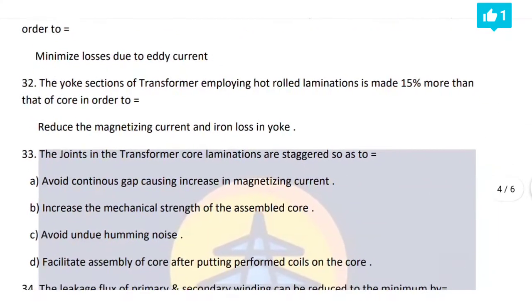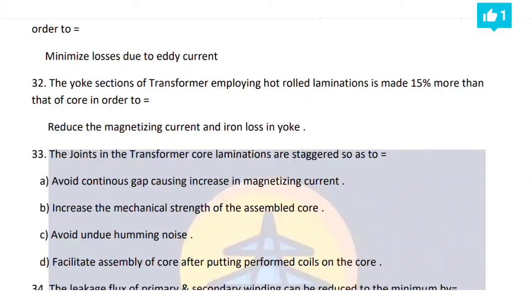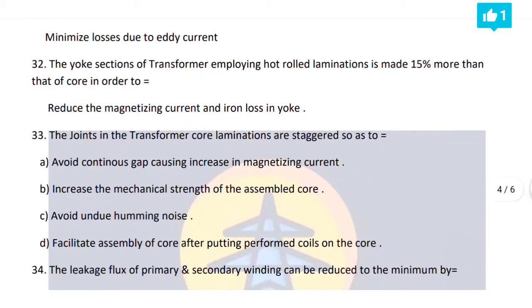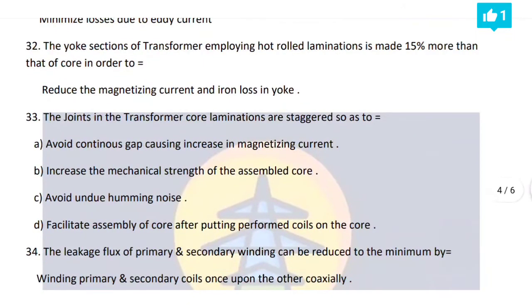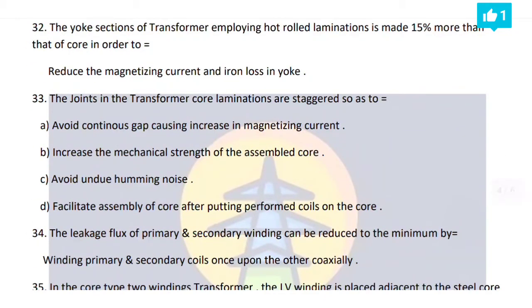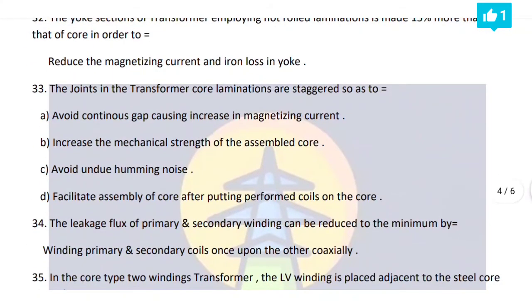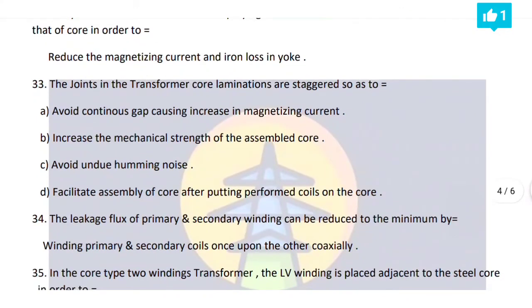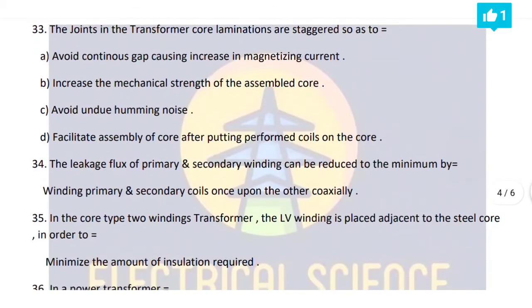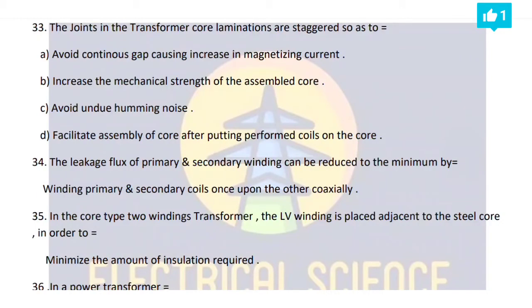32nd point, the yoke section of a transformer employing hot rolled lamination is made 15% more than that of the core in order to reduce the magnetizing current and iron loss in the yoke. 33rd point, the joints in the transformer core laminations are staggered so as to, first point, avoid a continuous gap causing an increase in magnetizing current. Second point, increase the mechanical strength of the assembled core. Third point, avoid undue humming noise. Fourth point, facilitate assembly of the core after putting performed coils on the core.